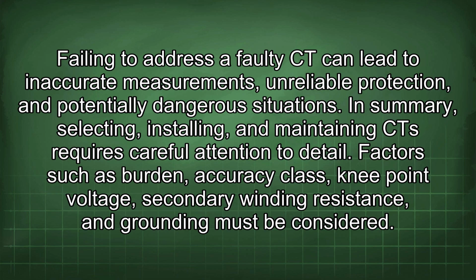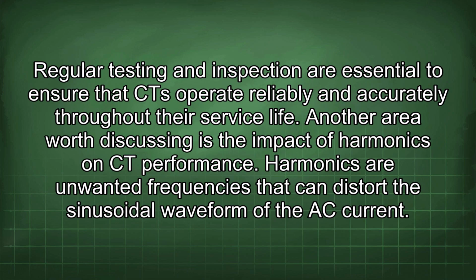In summary, selecting, installing, and maintaining CT requires careful attention to detail. Factors such as burden, accuracy class, knee point voltage, secondary winding resistance, and grounding must be considered. Regular testing and inspection are essential to ensure that CT operate reliably and accurately throughout their service life.